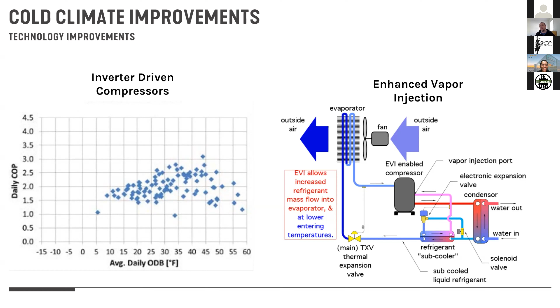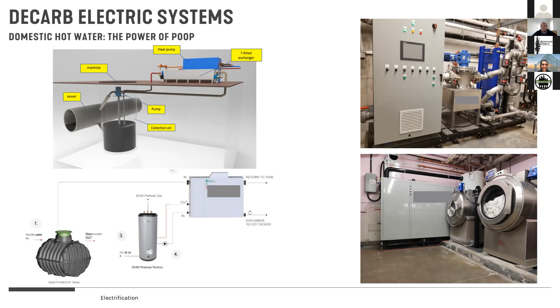So where do we go when the outside air temperature isn't that good? Well, we're super excited about looking at every other source on a building that we can get good quality energy. So in the case of domestic hot water production, I love to look for the sewer. How close is the sewer? How much volume can I store on site so I can extract the heat out of it before the effluent leaves the building? So we're heavily involved with applications of using both the SHARC and the Piranha from SHARC Energy, using those for domestic hot water production in very large scale facilities.